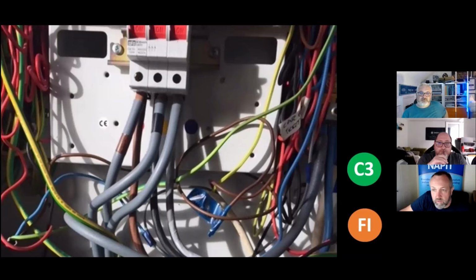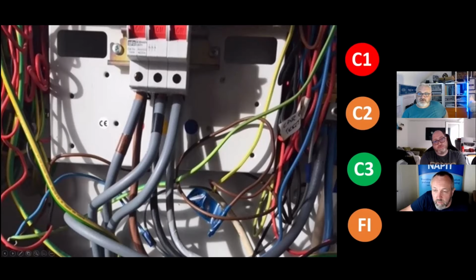Just all of the other stuff too, protection of the cables and so on, because these cables are going to go to another consumer unit, and for them to be adequately protected, they've got to come back from there and then back to wherever those are fed from, which may be acceptable. For me, it's a C2 as a minimum, but there's some FI in there with those cables tied up, taped up, and all sorts. There's a lot going on there.